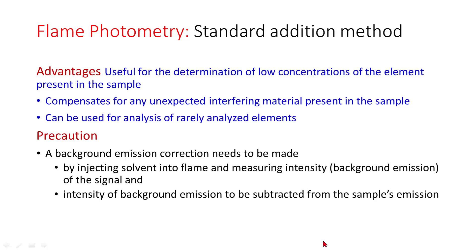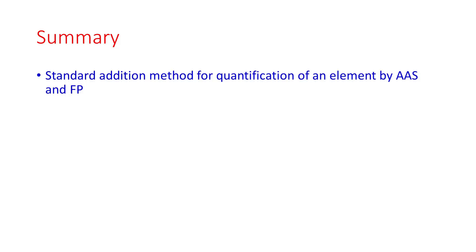Precaution: a background emission correction needs to be made by injecting solvent into flame and measuring intensity, that is background emission of the signal. And intensity of background emission needs to be subtracted from the sample's emission.